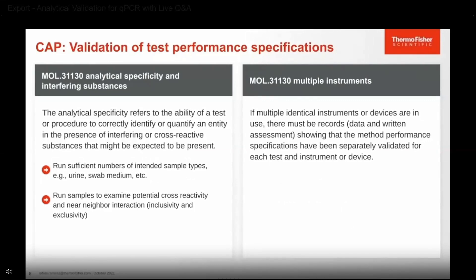In terms of analytical specificity and interfering substances, it refers to the ability of a test to correctly identify or quantify an entity in the presence of interfering or cross-reactive substances that might be expected to be present. Running sufficient numbers of samples of your intended sample type is key. You want to examine potential cross-reactivity and near-neighbor interaction to establish inclusivity and exclusivity. When it comes to multiple instruments, even if they are identical, there must be records showing the exact serial number that each instrument was separately validated.